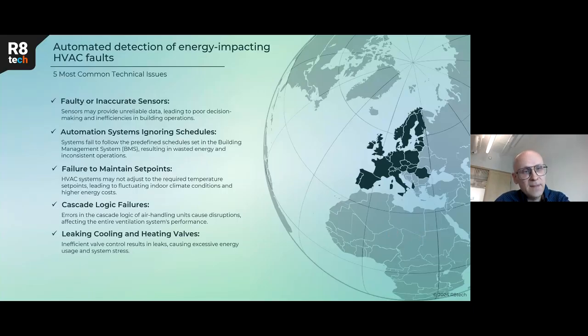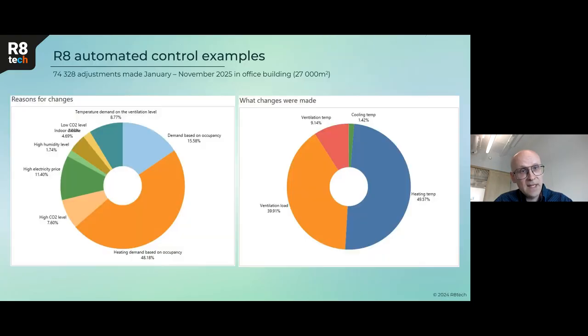And failure to maintain set points, cascade logic failures, leaking cooling and heating valves, etc. For example, leaking cooling and heating valves: besides the valve position, we are checking the temperatures as well to detect such issues. So in practice, this fault detection part is very useful for the maintenance staff. And for us, it's very important because these issues very easily could offset our savings or our impact. But yeah, let's move more to the console side.